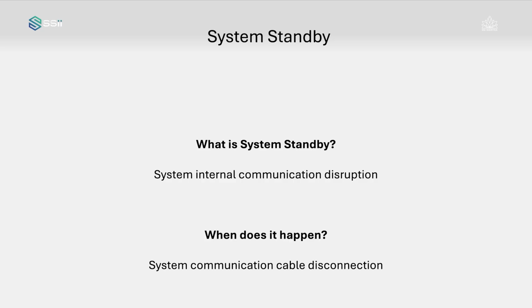Mantra surgical robot system consists of multiple communication cables internally as well as externally, which facilitate the communication between the components such as surgeon command center, vision cart, and patient side arm, as well as internal system components. If any of these communication cables are disconnected or disrupted, intentionally or unintentionally, the system may enter standby mode. In standby mode, the entire system is affected.